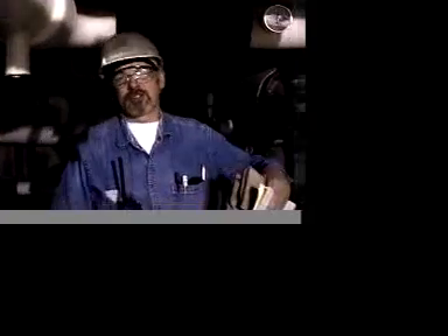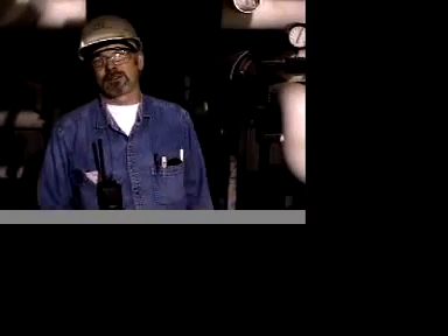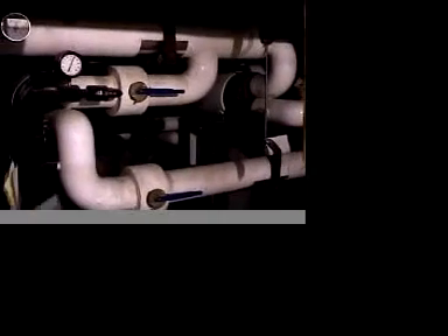Okay. Go ahead. These are your chill water valve or hot water valves. These are your ones you got to change every winter and summer. Right now they're open for heating. This is the one. Here's the other. There's one right back here. And these work in conjunction with, you can't see the handles on the back side. Right. These have to work in conjunction with those two chill water valves. Right. They should really all be open at the same time and shut the other one, whatever you're doing. And that just goes back to these two lines here. And then they're going into the air handler, through the heat exchangers, back out into the system. Okay. The chill water runs through the building the same way.